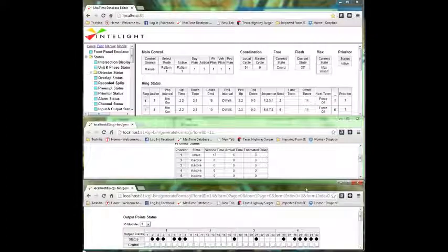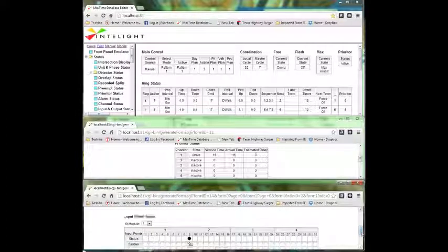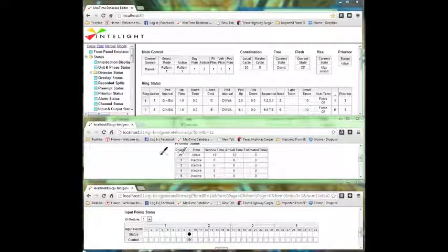So we're in 1 and 5, we hit apply, scroll down, I got my inputs true, it's active, the service time is going to be in that many seconds, arrival time, and I have no delay, which means he's getting through on the green. So he was right at the point where we didn't have to do an adjustment.